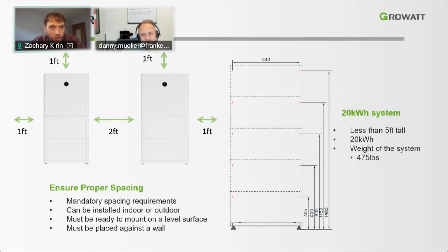It can be installed indoor or outdoor, thanks to that NEMA 4X rating. And it must be mounted on a level surface. It comes with a floor stand, which is adjustable, but we still want to make sure this is on a solid level surface and placed against the wall. A 20 kilowatt hour system is less than 5 feet tall, so it's really energy dense, but the weight is quite heavy. It's 475 pounds with the power optimizer on the top. Each of the battery modules weighs about 110 pounds, and the power module weighs 35 pounds. It could be a 2-man lift. I do know some who will definitely be able to lift this by themselves, but for installing this battery, just know your own limitations so that you don't overexert yourself while lifting up the heavy battery modules.